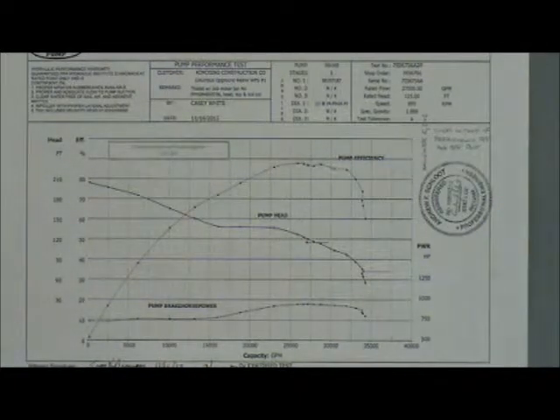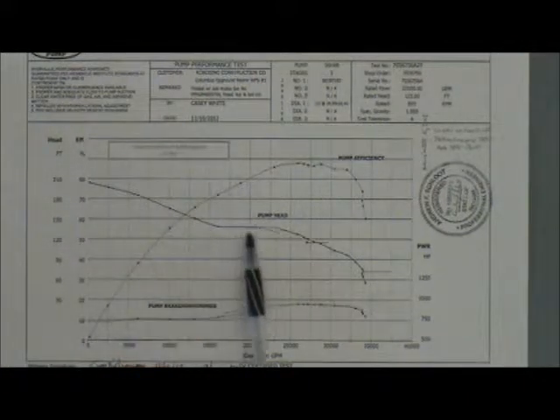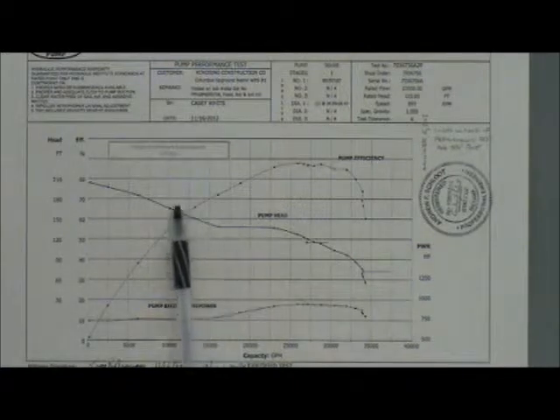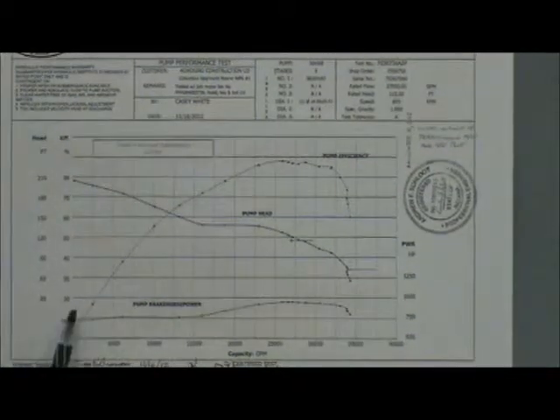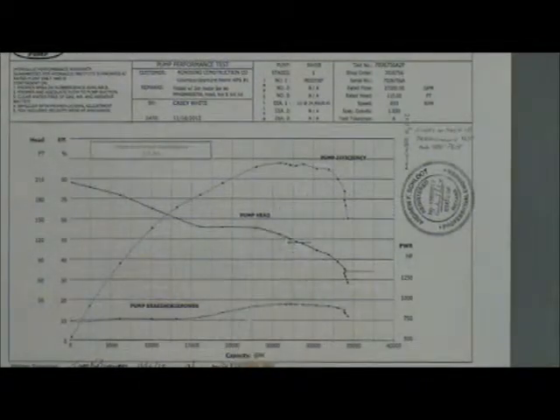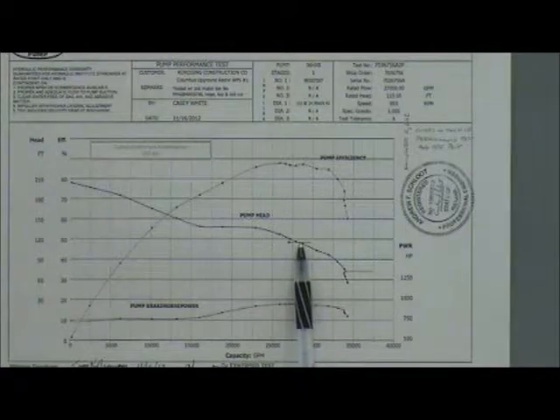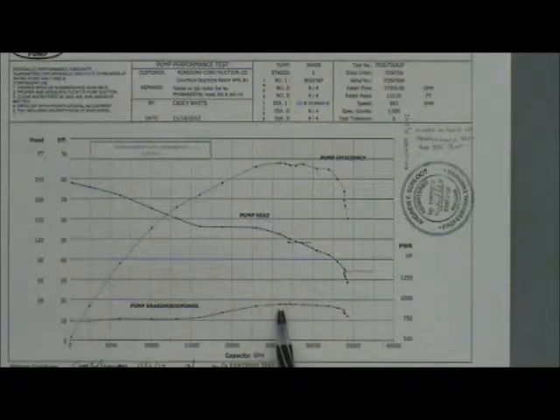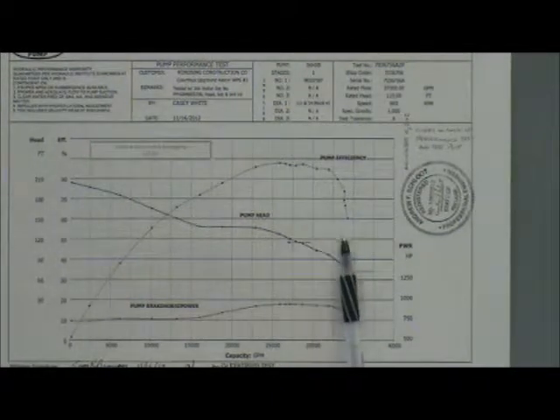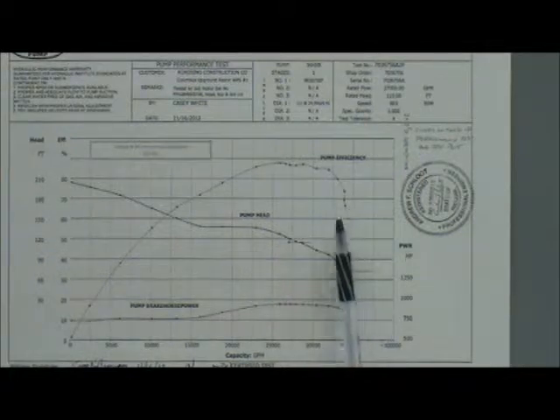And then there's also the ability to go into manual mode, and you can select anywhere along this curve through our control sequencing in manual. Two other things to point out on the pump curve are the pump efficiency and the pump brake horsepower. At our normal flow rate, you can see that we maximize our efficiency as well as our pump brake horsepower. But as you go out onto the pump curve, your efficiency falls off as well as your brake horsepower.